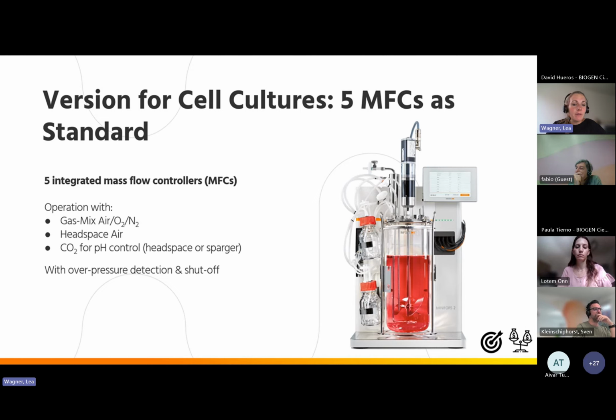And there's a 5th MFC for carbon dioxide, which is often or mostly used for pH control for cell culture processes. So instead of acid, because acid harms the cells. So for cell culture, the customers rather want to use carbon dioxide for pH control. That can be used either in the headspace or through the sparger. And of course, also for this version, we have the overpressure detection and shutoff. So this again fulfills the requirements of the customers to get the optimum conditions for their bioprocesses, and also total cost of ownership, because we have a very high standard here with MFCs instead of rotameters and magnetic valves.